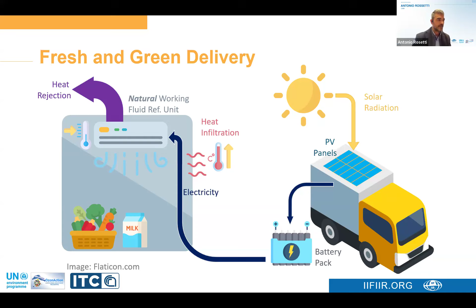We started by taking as reference the stationary application for commercial refrigeration with an ejector, and the challenge here was to apply this concept to a small power application—just 6 kilowatts of cooling power at standard conditions—and make everything work: the ejector for such a low capacity, and the control system able to manage the high pressure and the ejector itself.